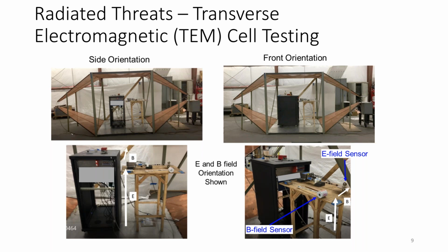So either the relay or the DCS component will be placed in that rack, and the field level is ramped up, and we look at the response, anywhere from no response up to destroyed. When we looked at the relays, they're pretty robust under this kind of test. We got to the very highest level of the test, above 30 kilovolts per meter, and only had some minor disruptions, a non-latching upset. With the DCS systems, very similar results: we got to the highest illumination levels and had non-latching upsets, but there was no destruction of equipment.